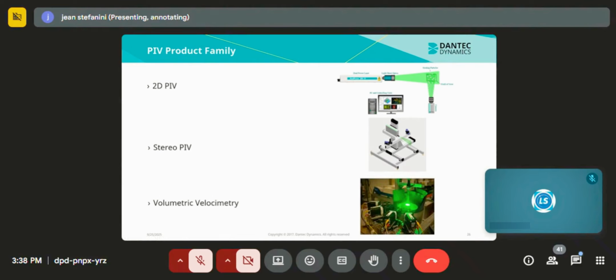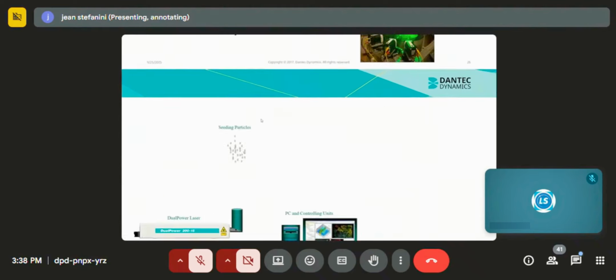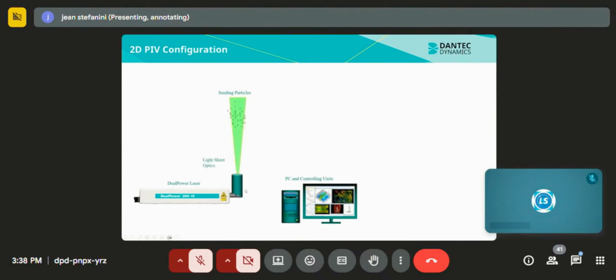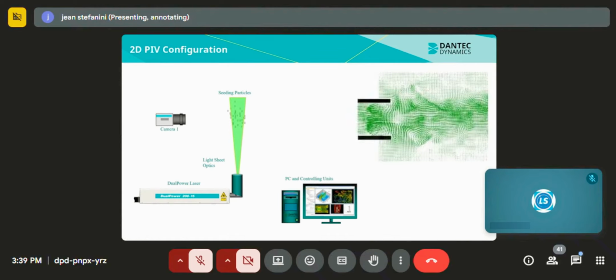And the last one is a volumetric approach where you have multiple cameras. So the principle, as mentioned before, we have a dual pulse laser. We have seeding particles for a 2D configuration. We have a light sheet optics. So light sheet optics is composed of a set of lenses to expand the beam and to focus the beam where we want to make the measurements. Then we have the camera that records the information, and everything is transferred to the computer, and the software will calculate the velocity field. This is what you will get here.